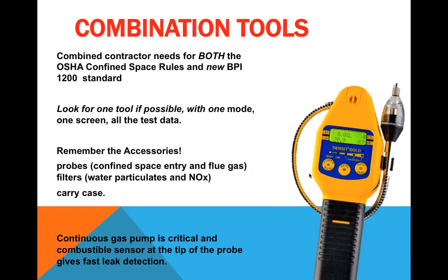So combination tool, we looked at this actually, it was almost a year ago when we saw the two standards kind of converging for the confined space rules from OSHA and the BPI 1200 standard. So we worked closely with SENSIT to create one tool with one mode, one display, all the data, with all the complete accessories for doing confined space entry, flue gas testing, filters for particulates, and NOx gas. Again, that's part of the BPI 1200. You want to filter NOx before you measure CO, and even a carrying case.